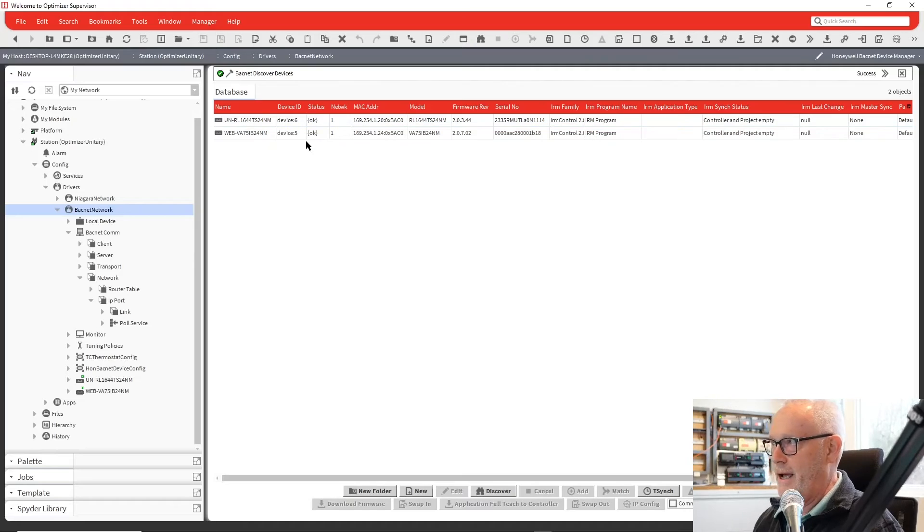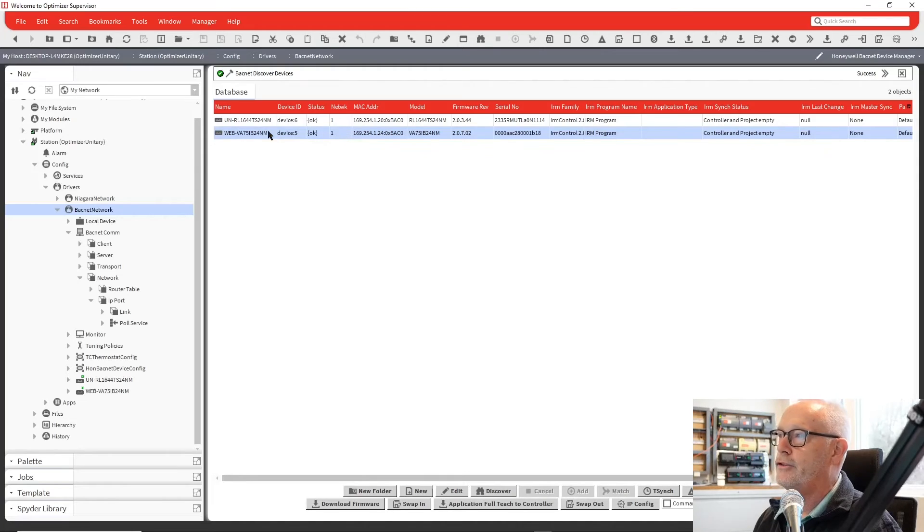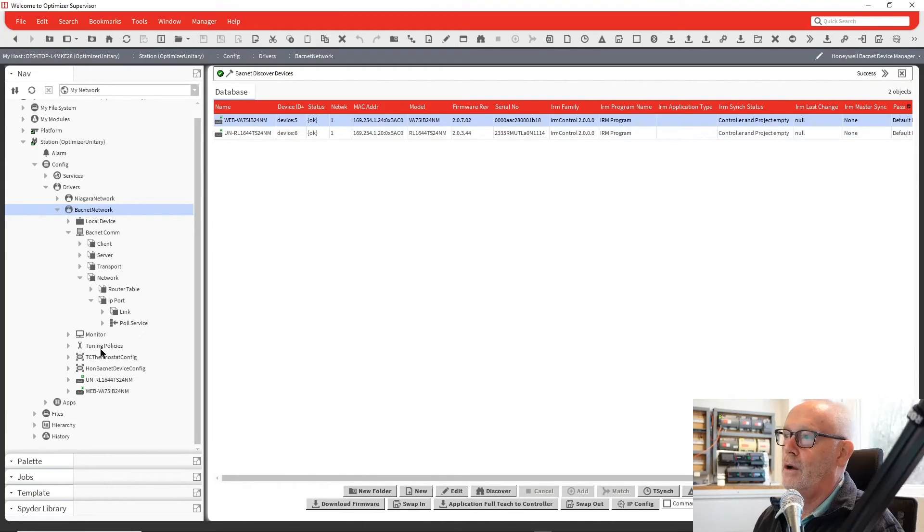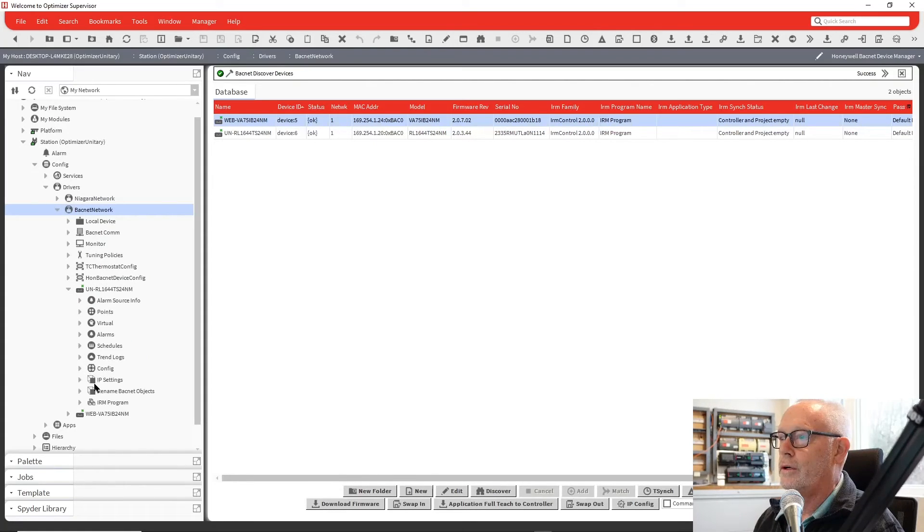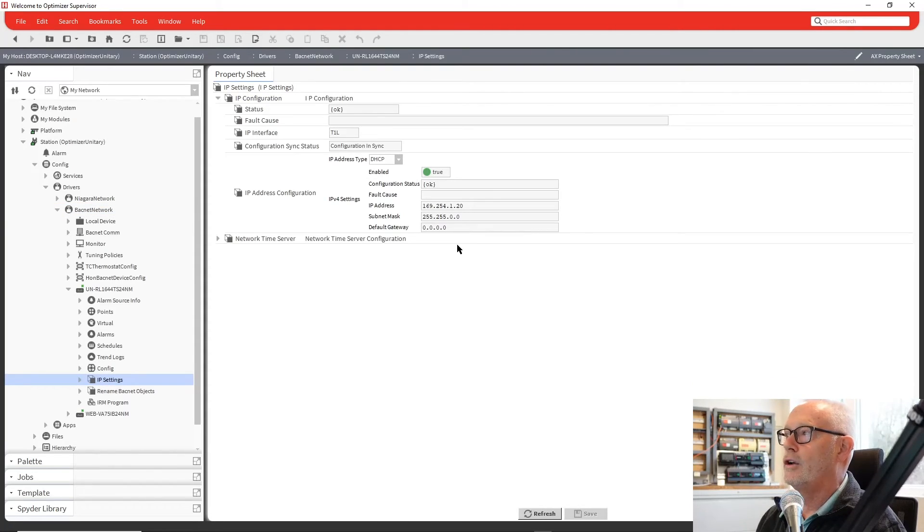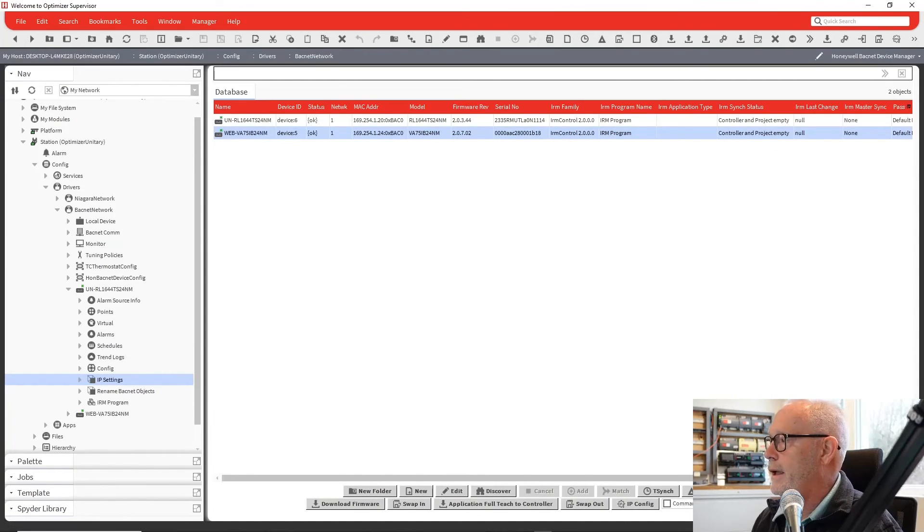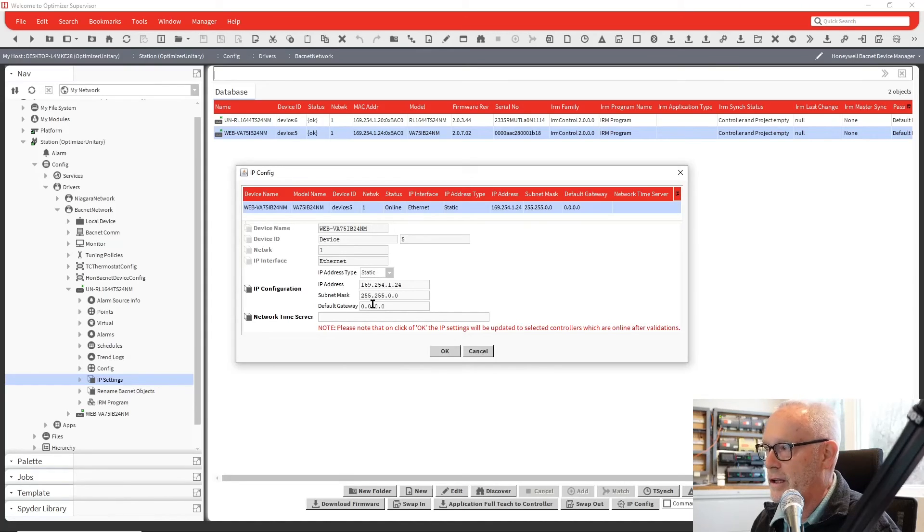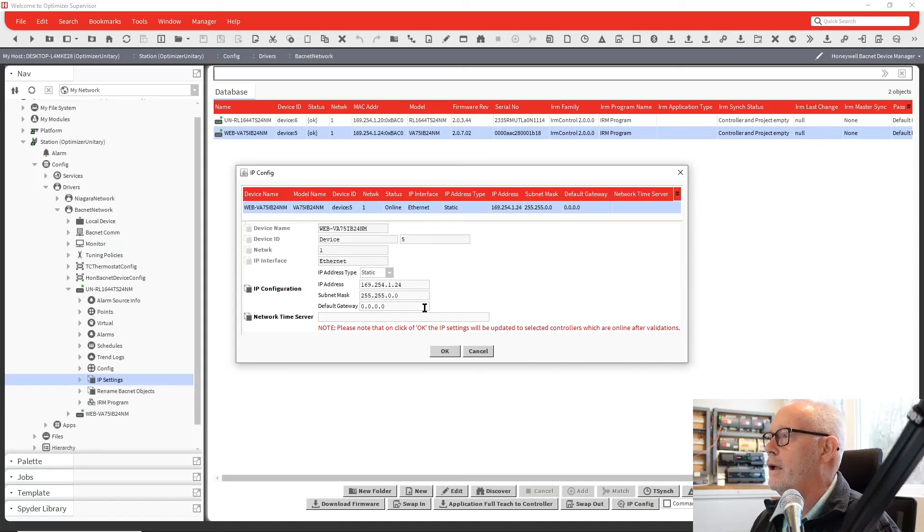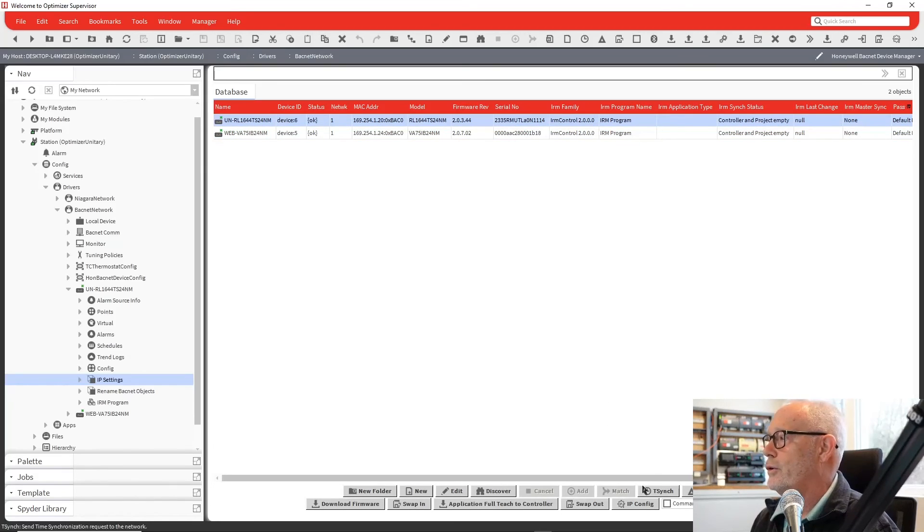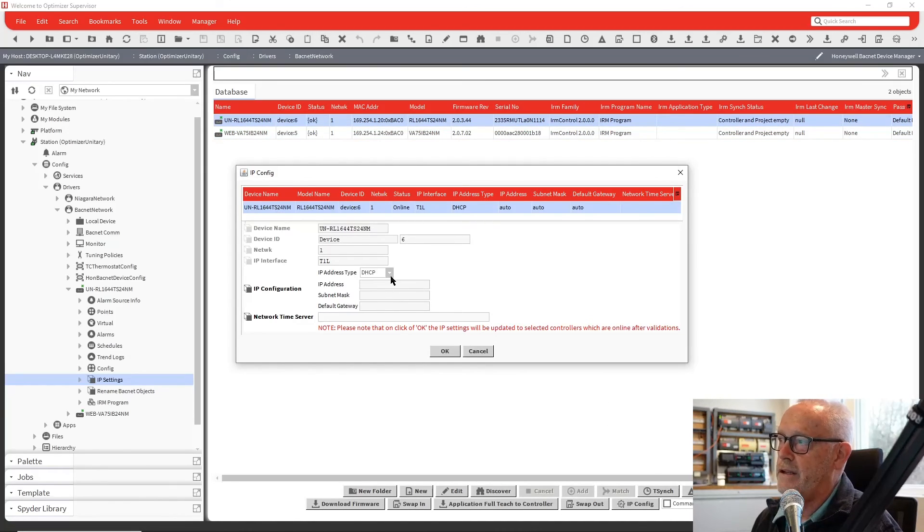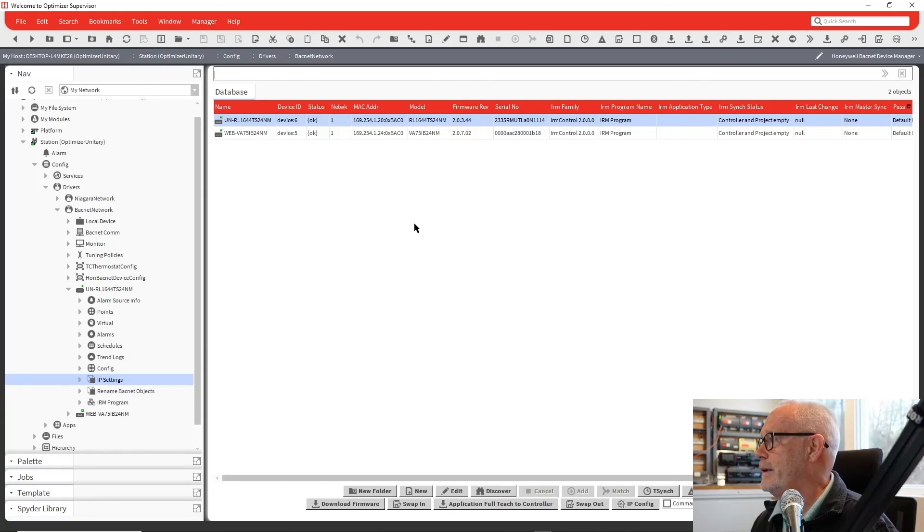But let's say now we're at the point where we don't necessarily want to keep this IP address scheme. So we could go in one of two ways. We could come over here into our nav tree. We can go down into a controller. We can go to IP settings from there, and actually make our changes from that screen. Or back on the device manager, we take a controller, and we go down and select IP config, and this will allow us to go in and change it to a static IP address. We can make it whatever we want, whatever is required for the job site. And when you hit OK, it's going to update all that for you. And then do the other controller as well. And off to getting this all set up and get your programming done and commissioning the system.